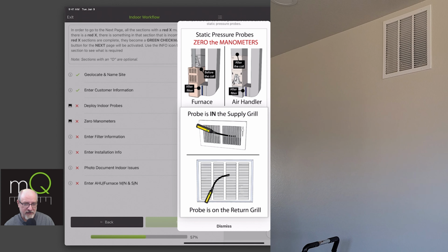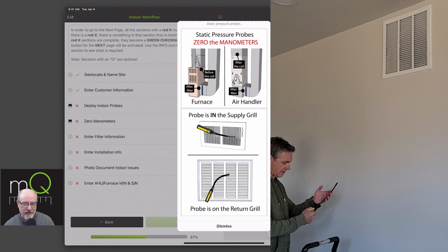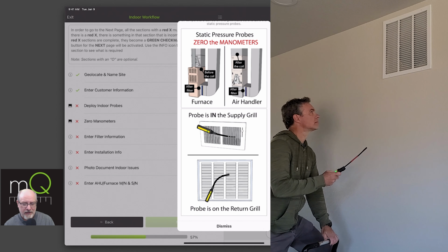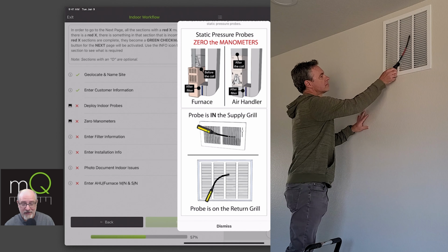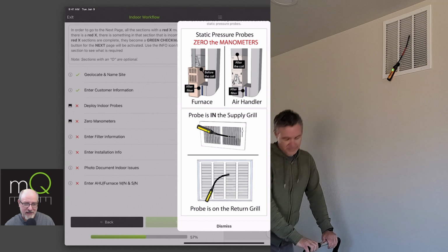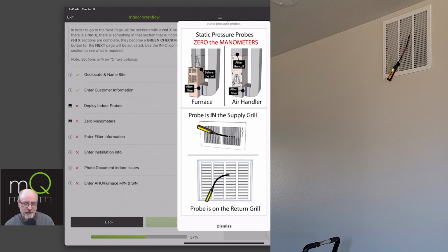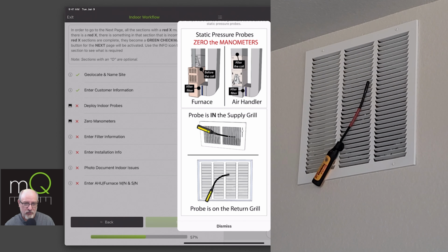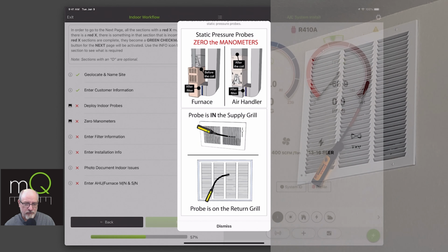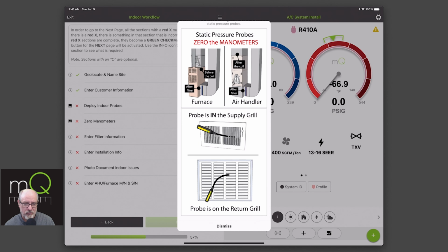You can just put that on the return nearest the air handler. I don't recommend a return grill in a basement because you're not getting a good establishment of the real return temperatures as you would upstairs, so I encourage you to use upstairs as your probe placement. There's a variety of options for return, but in general the return grill nearest the air handler is what you're after on the face of the grill. That's upstairs if it has a basement.